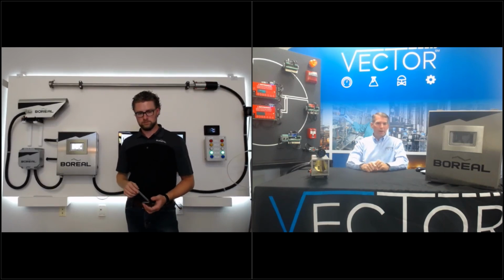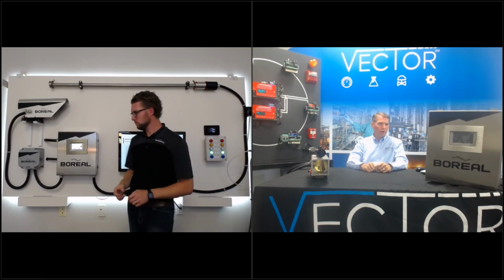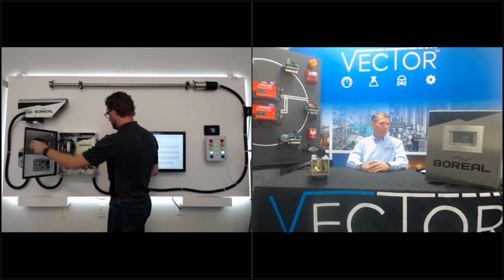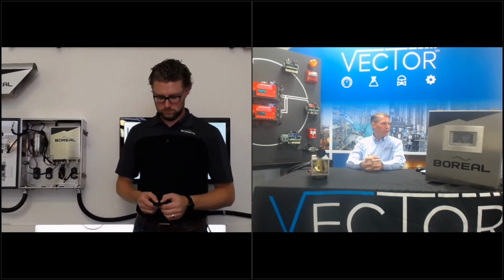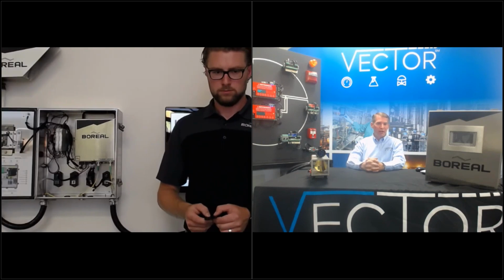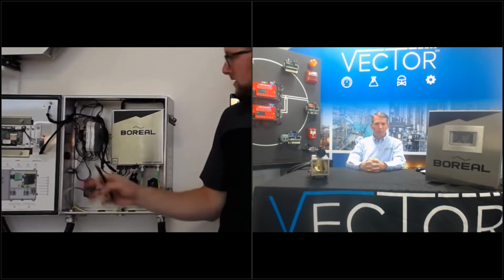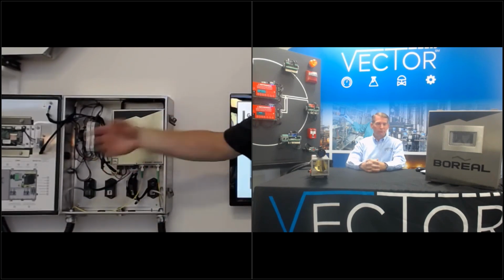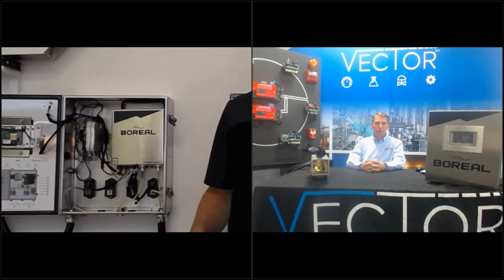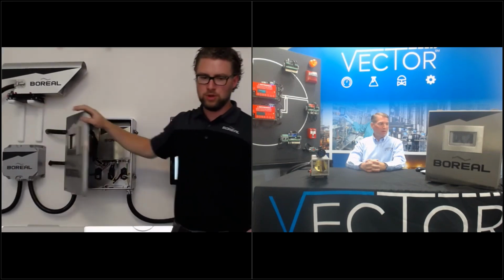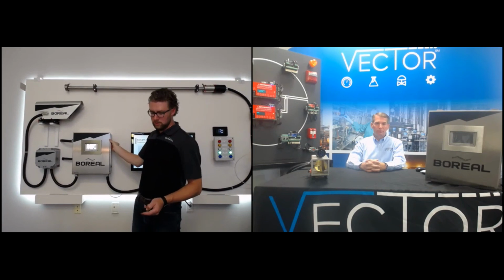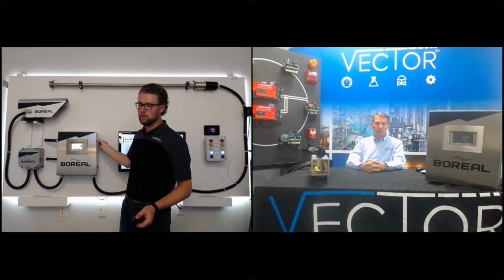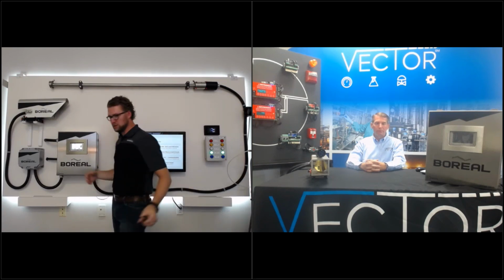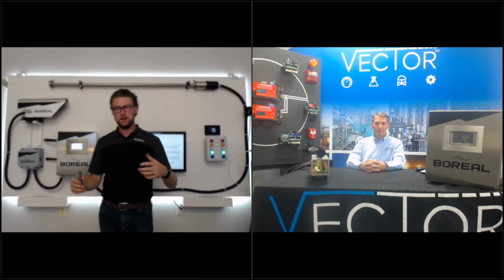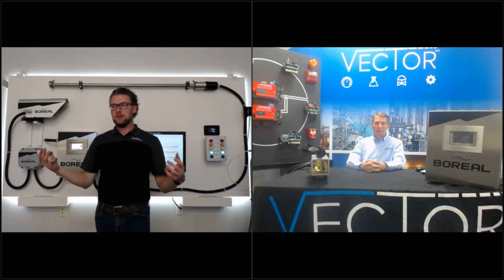The other thing I wanted to touch on real quick, Kyle, that I don't know if we covered or not: if you open up the front door, there is a USB port inside the unit so you can extract the data out of the unit. I don't think we talked about pulling that data out and how much information is really available for the customer. Yeah, so inside the unit, just on the side here, you can connect a USB stick and download all of the generated data from this system. The system has its own built-in internal historian that can run for 20 years straight and collect and store all of its generated data. The nice part about this is there's nothing redacted, nothing hidden here. You as an end user have access to the exact same data that we do at the factory. So nothing's hidden.